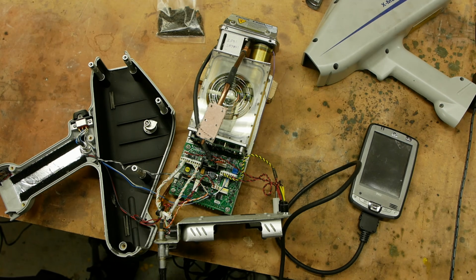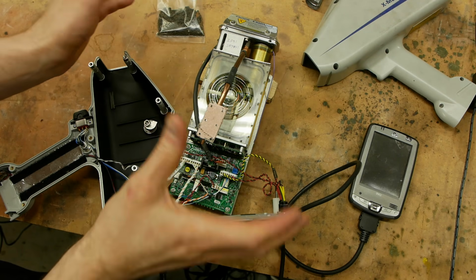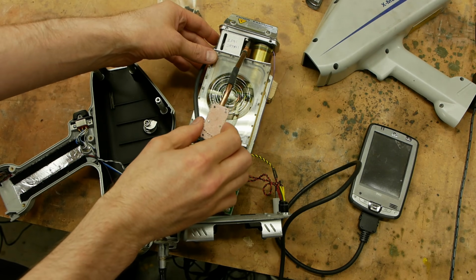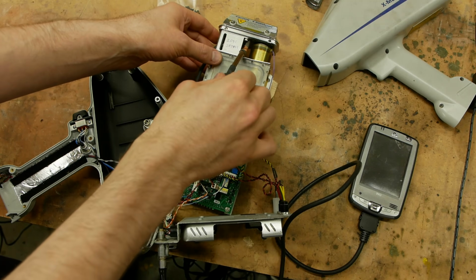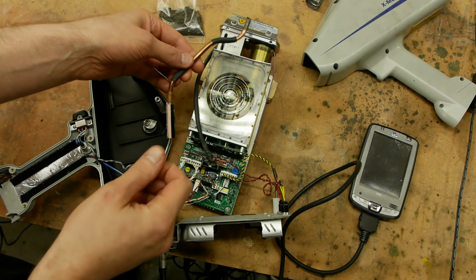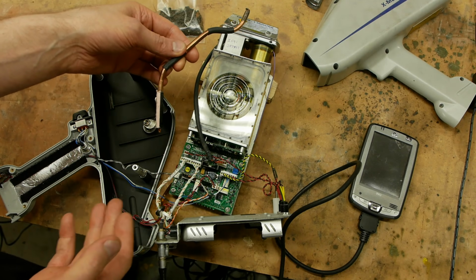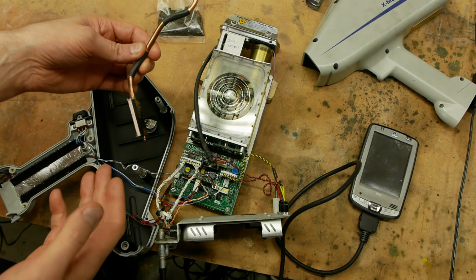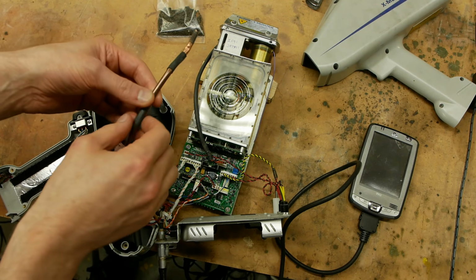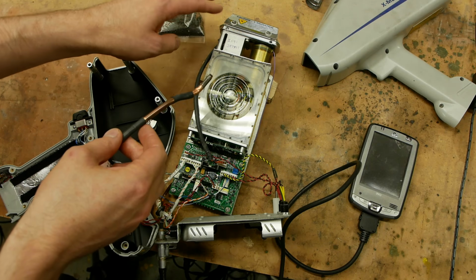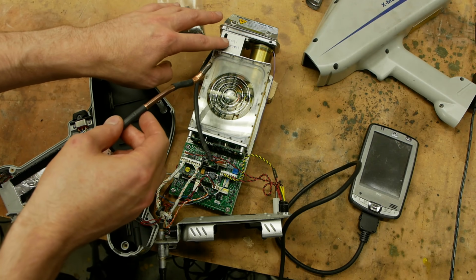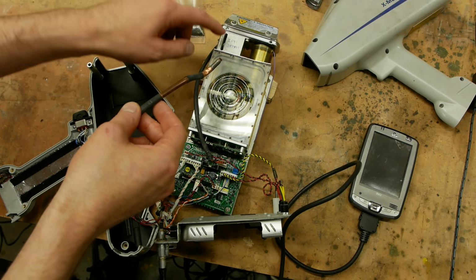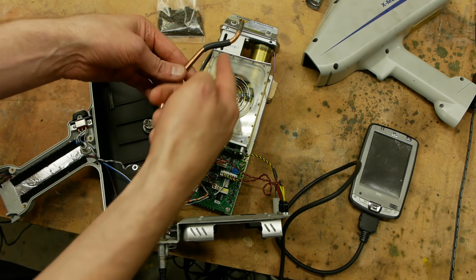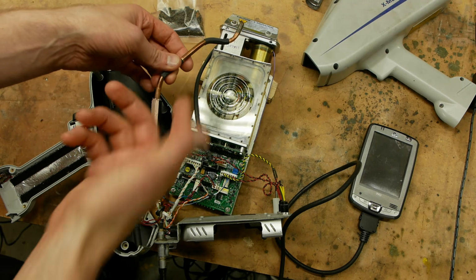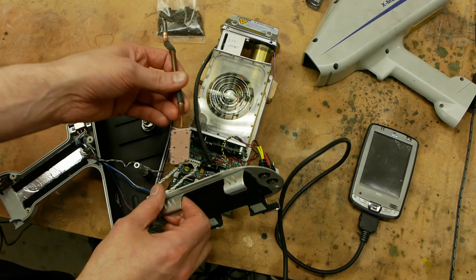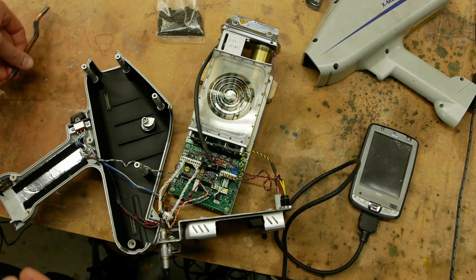Okay, let's see what's inside these magic devices that lets them work. I've already taken this one apart and taken all the screws out just so it's easy to pull apart. This first thing sticking out is just a heat pipe. The sensor that does all of this photon counting in the X-ray range probably needs to be cooled. There's no external cooler in here, but I suspect there might be a Peltier junction inside the detector, which is going to heat up and pump the heat out into this outer metal thing. Then there's this funny heat pipe to get the heat out of there, and it actually transfers it up to this metal plate behind the computer.